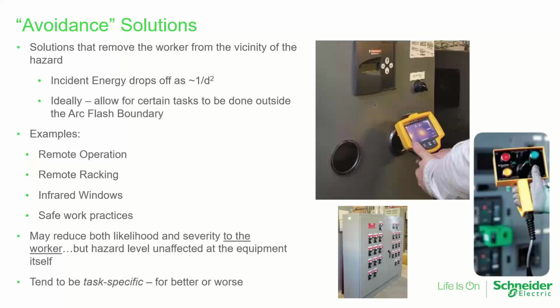If you haven't seen it, go to the search engine of your choice when we're done and search for arc flash racking breaker, and you'll see what can go wrong in those cases. Certainly much better to be able to do that from the end of some kind of control pendant than when you're standing right in front of the gear turning the crank to get the breaker to go in. Infrared windows, or even the more modern equivalent, thermal sensors that can be embedded in the gear, partial discharge sensors. There are a lot of things out there that continue to be developed and worked on that can help us do some of the maintenance tasks that we'd like to do while reducing the potential exposure of the worker. So these are great. They may reduce both the likelihood and severity to the worker.